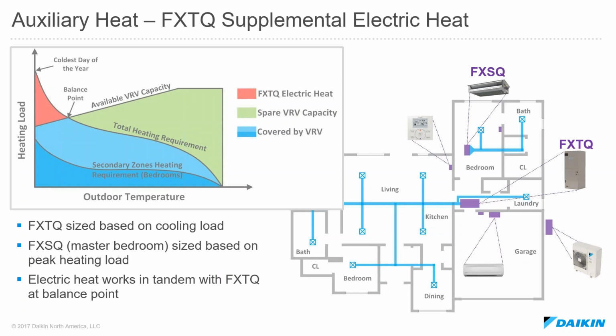So now we're going to look at another example, but this time supplemental heat. The FXTQ, like I mentioned earlier, is a good example of supplemental heat with an electric heating source. So we're looking at that same example we looked at earlier with the gas furnace and A coil, except we've switched the gas furnace and A coil with an FXTQ with some electric heat. So very similar scenario. You'd size this unit based off of peak design heating, and then this unit you could size based off of cooling, keeping in mind that you have electric heat as backup, provided you were in a climate and application that needed that backup heat.